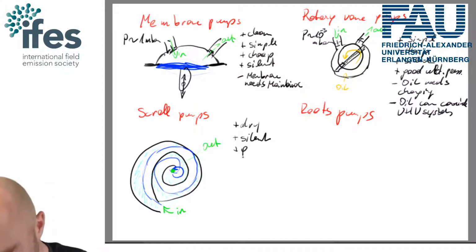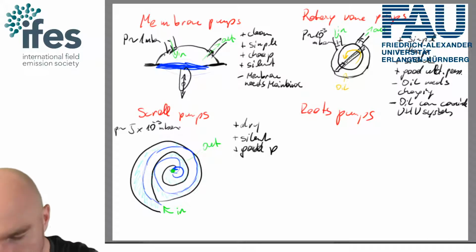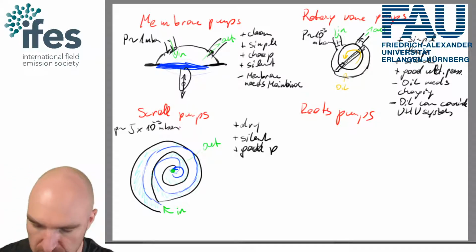Very good pressure. We usually end up at about 5 times 10 to the minus 3 millibar. So a bit worse than on the rotary pumps, but still quite okay.